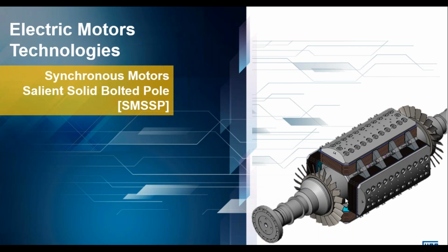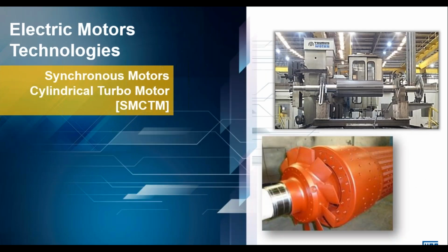So for applications where you need multiple starts, this synchronous motor design is a no-go. Where you start this machine and it runs continuously unless there's a problem, this is a synchronous motor design that you can consider. This is just an example of a smaller cylindrical synchronous machine.